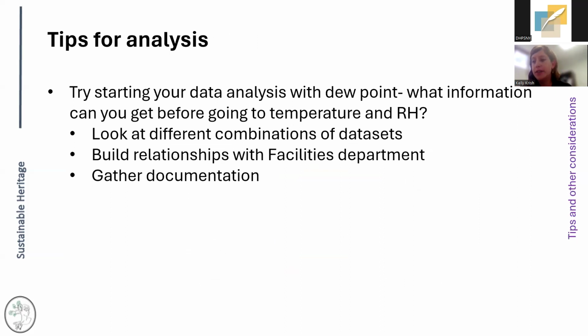Okay, in terms of tips for analysis, hopefully this has been helpful, but just to go over it again, I would try starting with dew point and think about what the dew point is showing you before you even look at temperature and RH. What are you anticipating? What are your concerns going to be at which times of year? Definitely look at those different combinations of data sets. Usually it's easiest to start with outside air and then work through those levels of control, following the path of the air through the air handler to the different spaces. Are the spaces that you're expecting to be similar actually similar? Is there an unexpected load that you need to track down the source of?